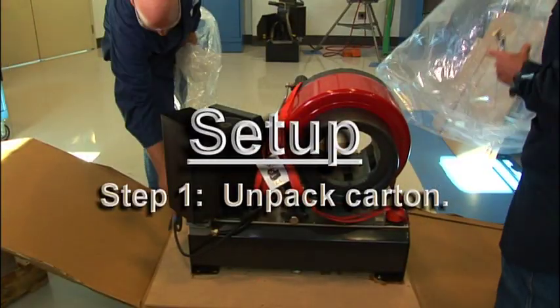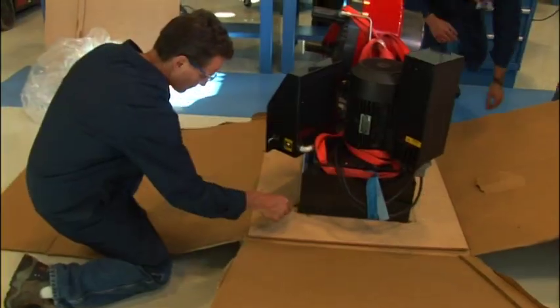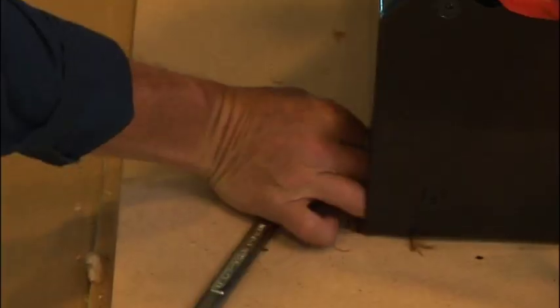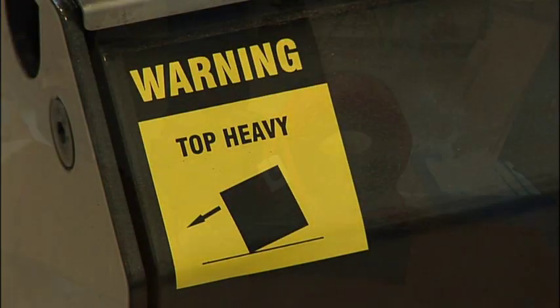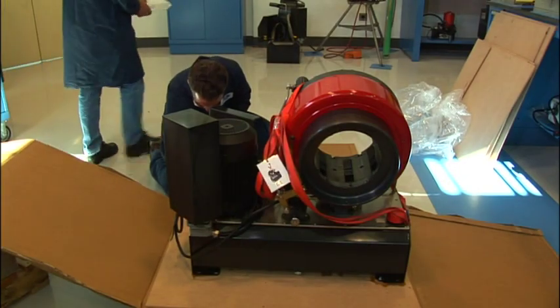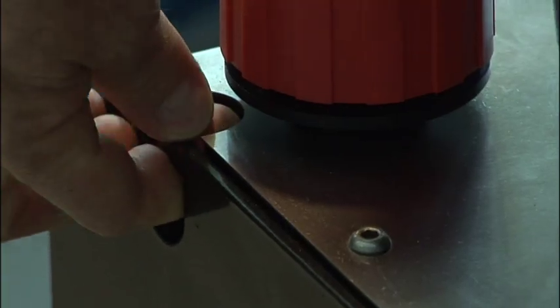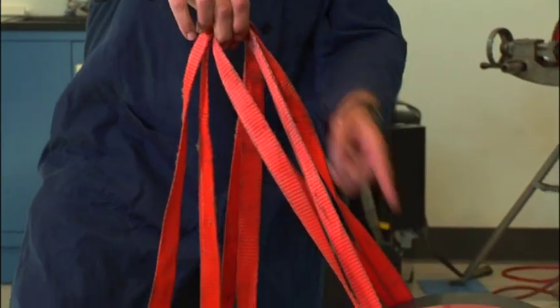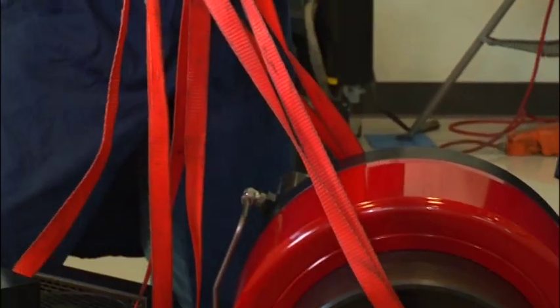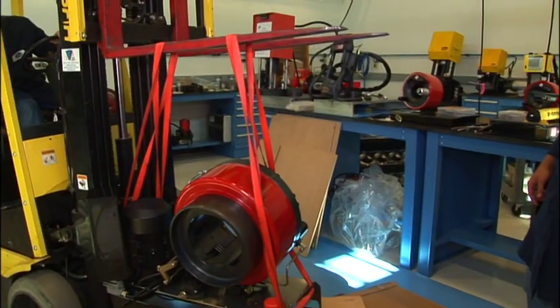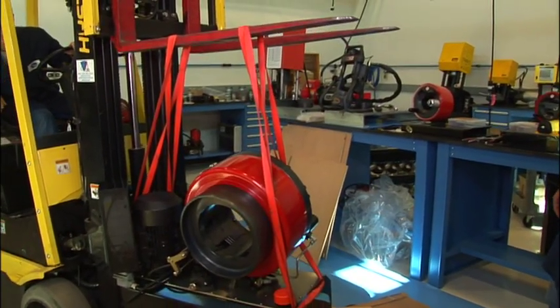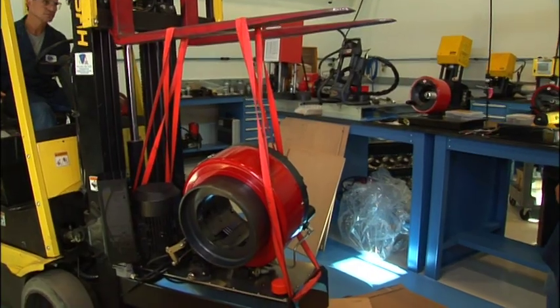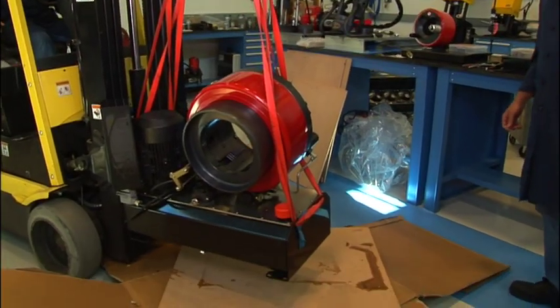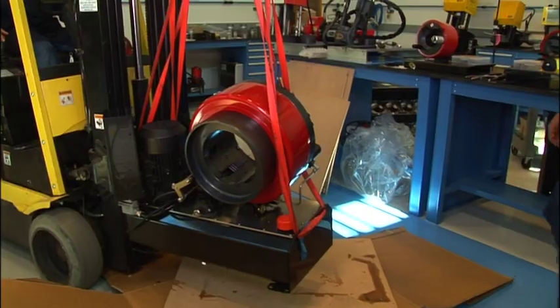Setup. Step 1. Unpack the carton and remove the bolts connecting the crimper to the pallet. Use caution as the crimper weighs over 800 pounds and is very top-heavy. Do not lift the crimper by the head. Use the lifting anchors on the crimper base. Using the included nylon slings and an engine hoist or similar piece of equipment, suspend the crimper and remove it from the crate. Locate the crimper's serial number on the rear of the reservoir base and record it and the purchase date in the spaces provided in your operator's manual for future reference.